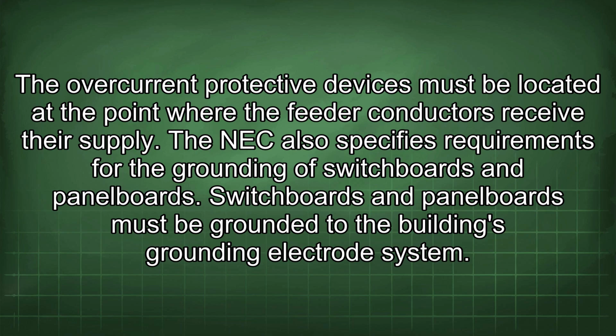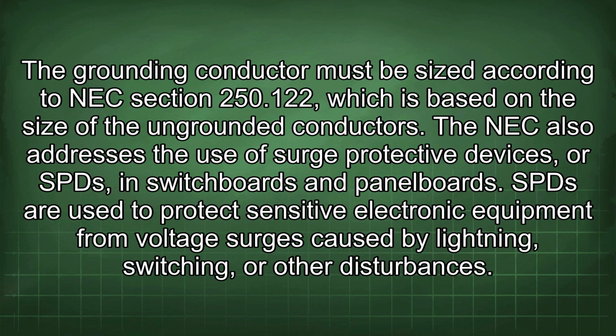The NEC also specifies requirements for the grounding of switchboards and panelboards. Switchboards and panelboards must be grounded to the building's grounding electrode system. The grounding conductor must be sized according to NEC section 250.122, which is based on the size of the ungrounded conductors.